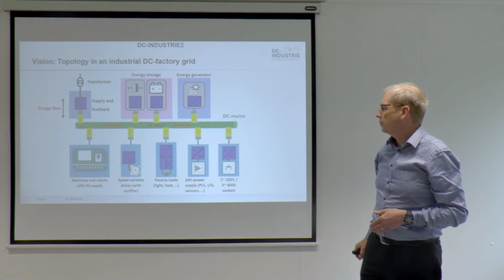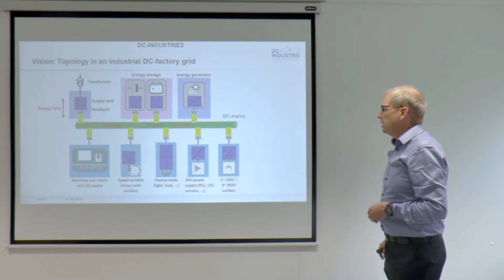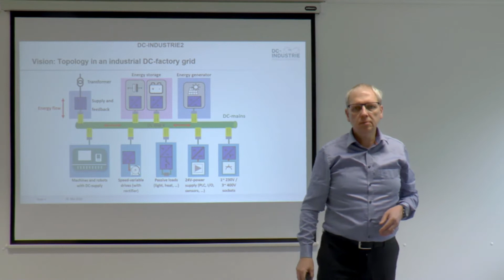Our vision is that we can change this topology into an industrial DC factory grid. This grid consists of the main part, a DC mains. You see the value of 650 volts. It corresponds with a rectified 400 or 480 volt AC system. On the supply side, you have a feed-in, uncontrolled or controlled. Inside the DC grid, you have a lot of consumers, for example machines, speed drives, variable speed drives, or passive loads, and especially 24-volt power supplies.